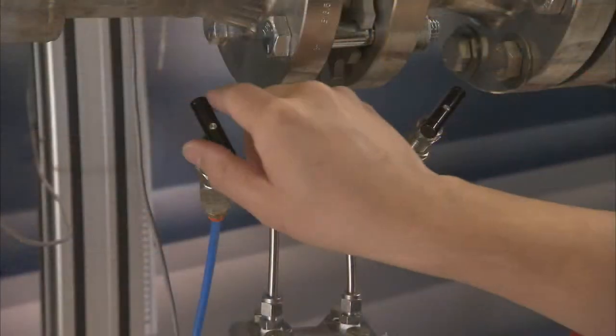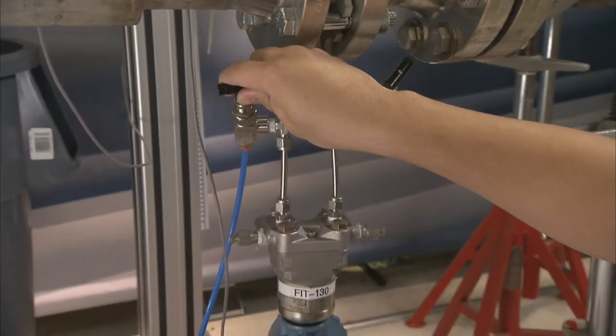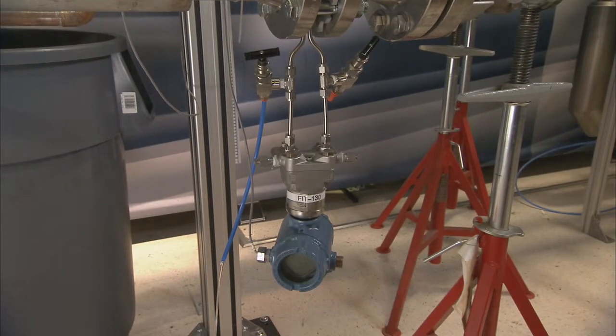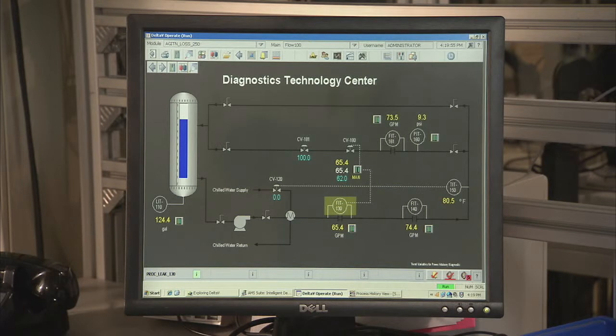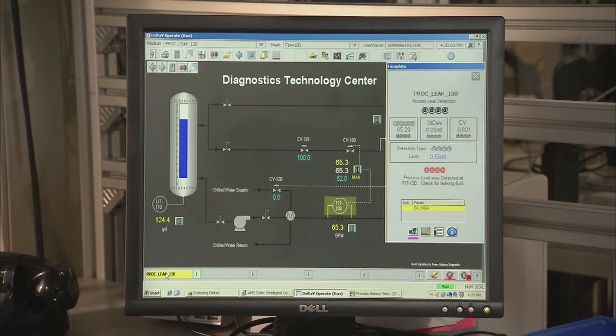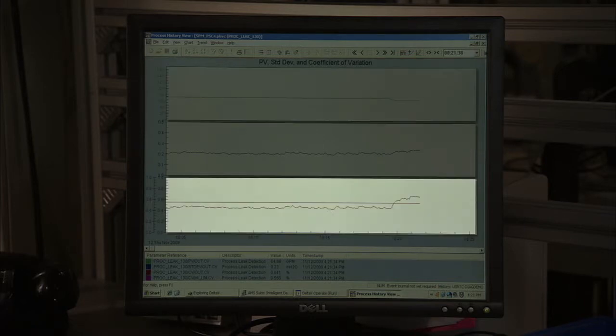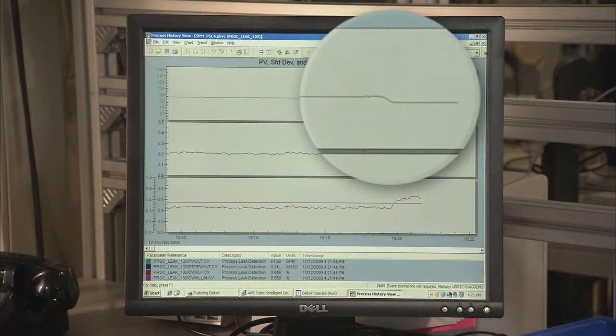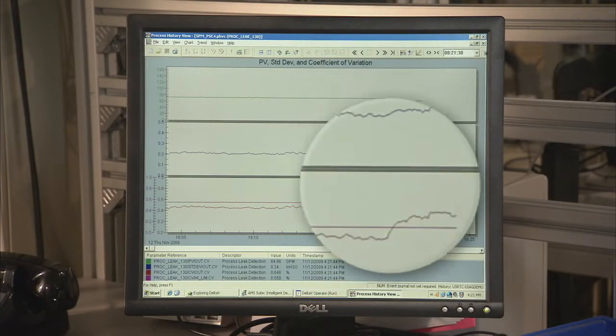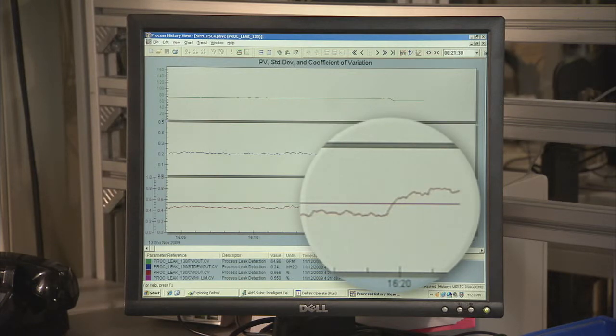To illustrate the process leak issue, we will create a leak in the impulse line leading to this 3051S with advanced diagnostics. As you can see here, the PlantWeb alert is flashing on the alarm banner, notifying us of the situation. By clicking on the alarm banner, this allows you to investigate further and gives you full access to the diagnostics information. Here, we can see that in addition to measuring pressure, the 3051S is also measuring the amount of process variability. This allows us to trigger an alert when the variability deviates past a predetermined threshold, indicating a process leak.